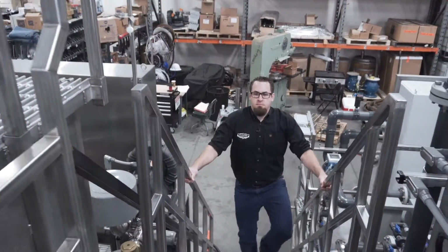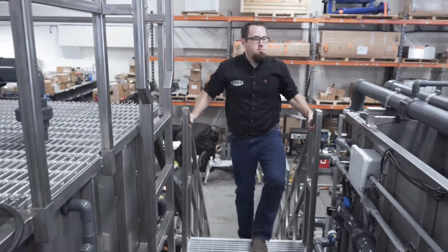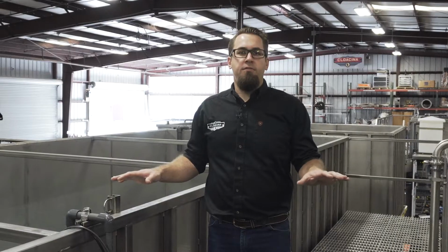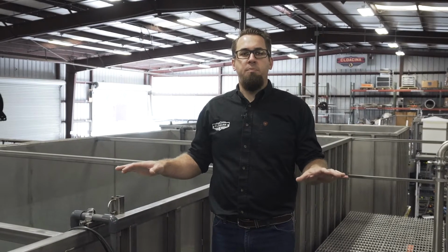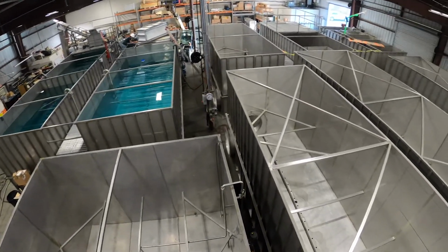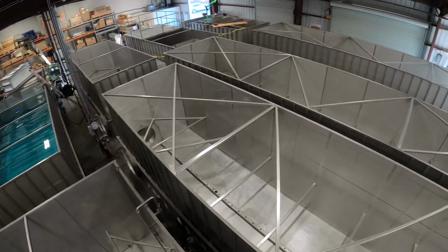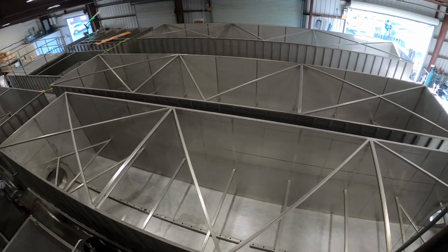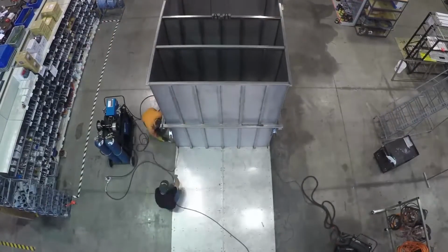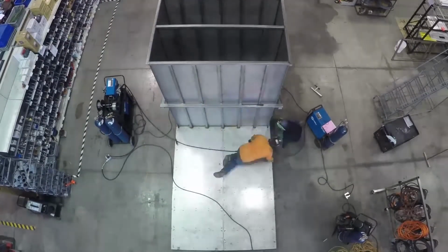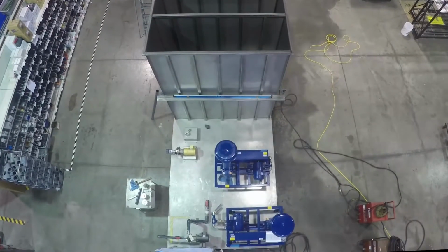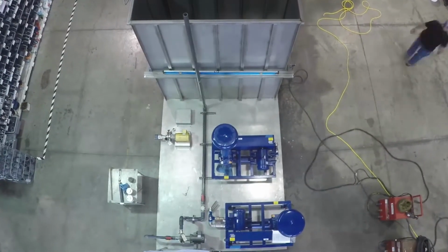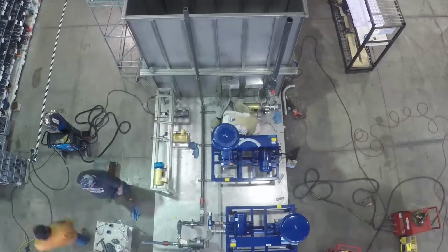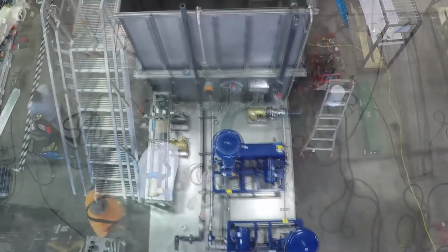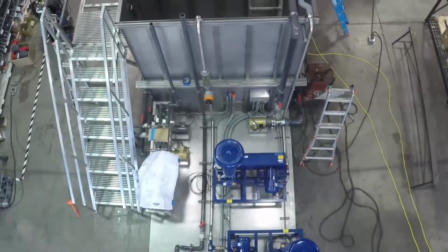We're standing now on top of the Mempak M75K. This particular plant is rated at a 75,000 gallon per day municipal spec influent and produces Title 22 quality effluent. When you take a look at the tanks that we're standing on, as well as all of the tanks that are in the background, 100% of them are built out of stainless steel. It's the only thing that we build all of our tanks out of. As a result, we avoid any cross-contamination with carbon steel. We are the only manufacturer in the world that builds 100% of all of their tanks out of stainless steel.